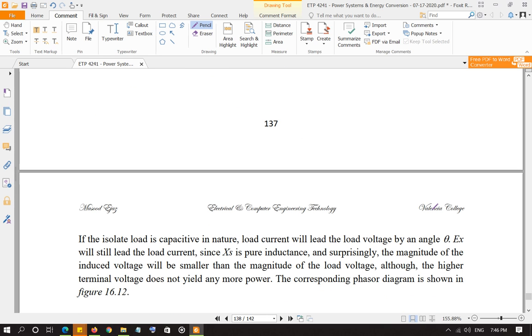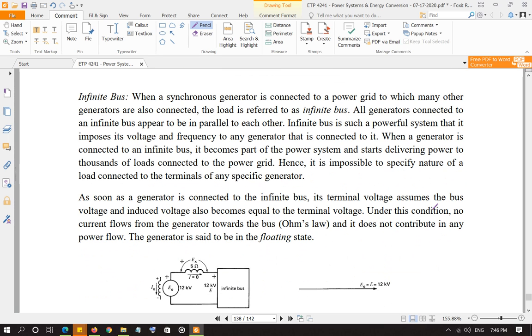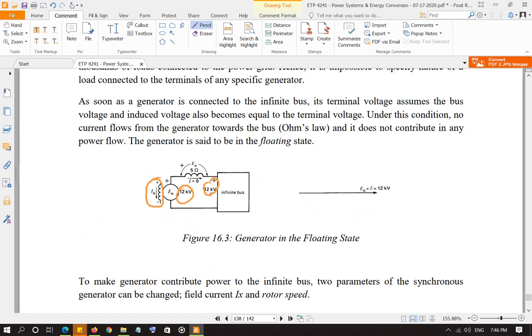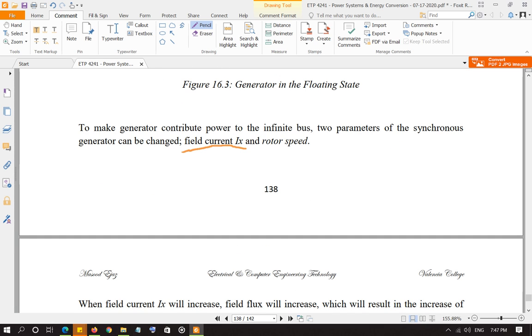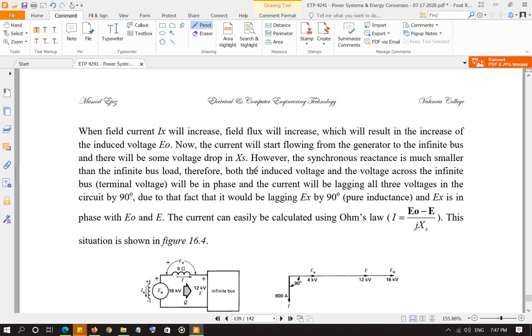So how does power flow from the generator to the grid? There are two ways. The first way is to increase the current to the electromagnet — that is the rotating field. When you increase that current, the flux is going to increase, and that flux will increase the induced voltage value. Right now the circuit is floating: 12 kV here, 12 kV here. E0 and E are both 12 kV, and I is zero. Once you increase the field current Ix, you increase the flux and you increase E0.